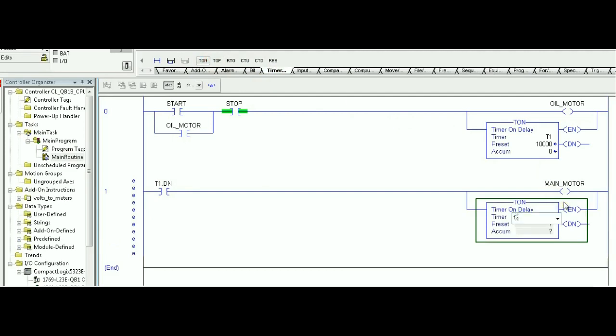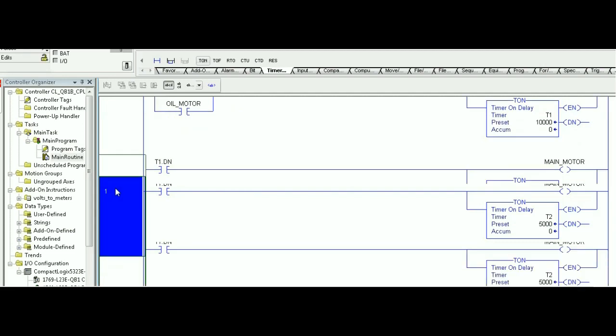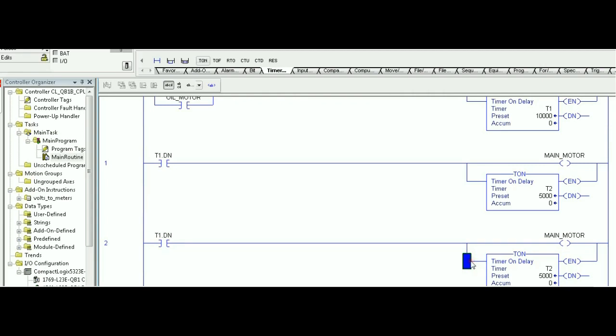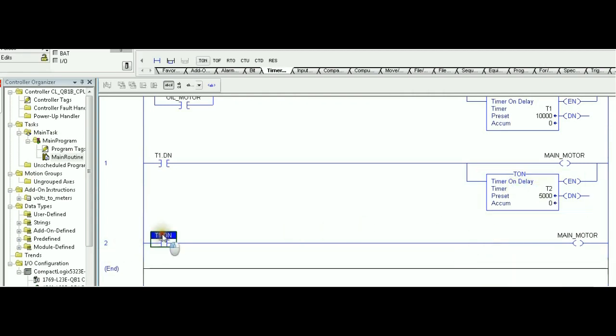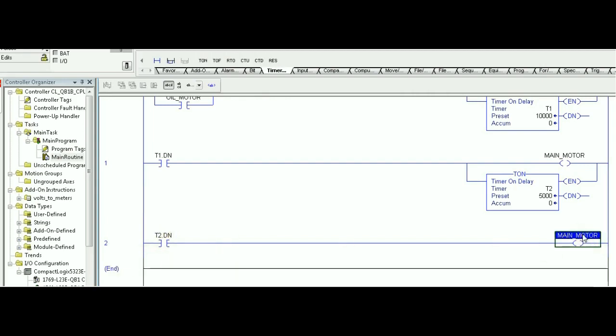I'm going to have the timer, timer 2. Timer 2, and this one will have a preset value of five seconds. And I can make it equal to zero. I like to use copy and paste a lot. Control C and V. And then the third, the last rung, we are going to have the timer 2 done bit. So, I will need to fix it over here. Please watch out when you are doing copying and pasting. You might just keep the same input on the pasted rung. The done bit will trigger the last motor, which is the auxiliary motor.